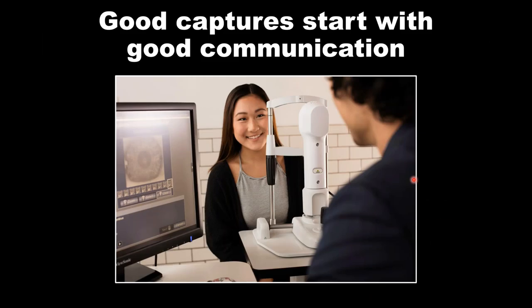A good capture starts with putting the patient at ease. Adults are somewhat used to instruments coming toward them, but explain that this is just a camera and it's not going to come near their eye. This is especially important with children in orthokeratology pre-fitting, who can be as young as six or seven years old. Research from Hong Kong Poly showed younger patients tend to have less accurate topographies because they're fidgety and move around, so communicate clearly that all the instrument does is take a photo.